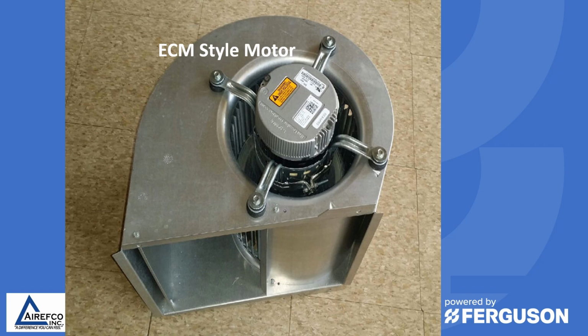But high voltage is supplied to the ECM motor at all times, and then there are communication lines that send the command to the motor to run. So yes, you need the high voltage to power the electronics in the back end of the motor, but you also need the communication signal from the control board to command the motor to run at whatever speed it needs for that particular mode of operation.